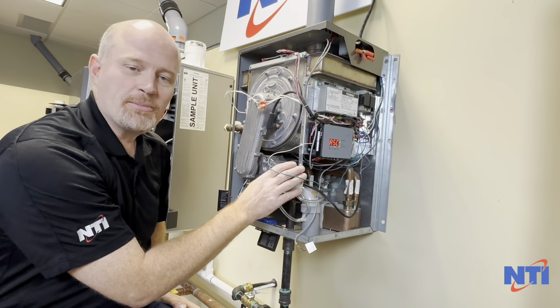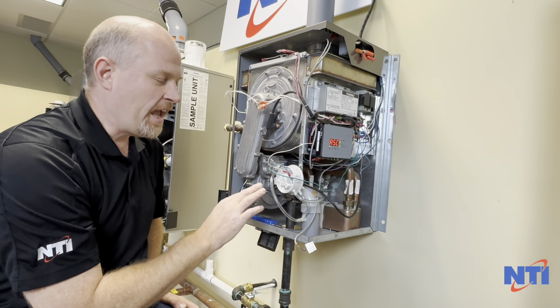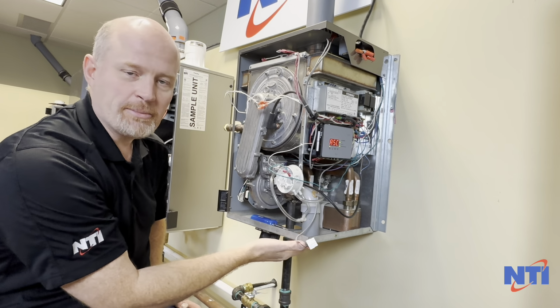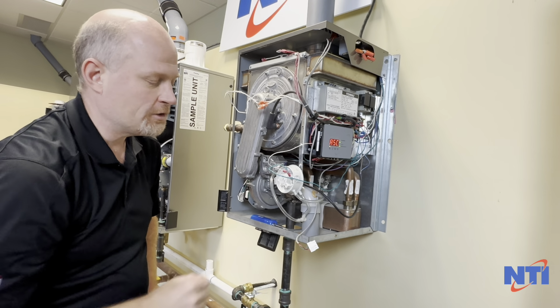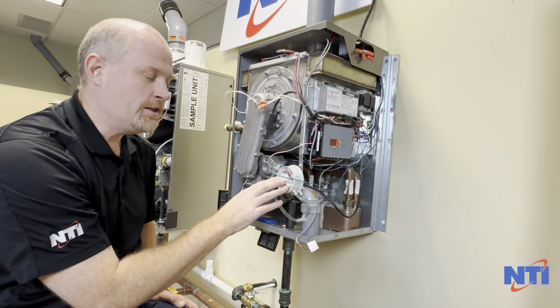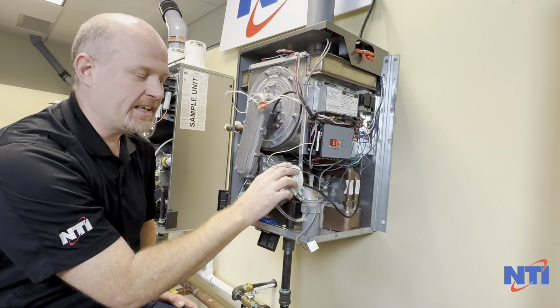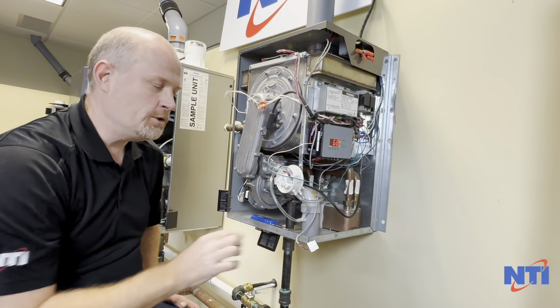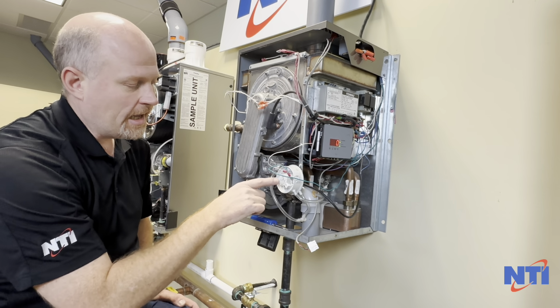So we've gone back to an ASC code. What that means is something's holding the air switch closed, and for the purpose of this video, we actually have a fan that's generating some airflow through our unit, and that's why the air switch is closed. The air switch here actually works fine, but in the field, what you might find is, again, if this gets bumped harshly or something, there's a little spring inside that can break loose, and then it'll stick closed.